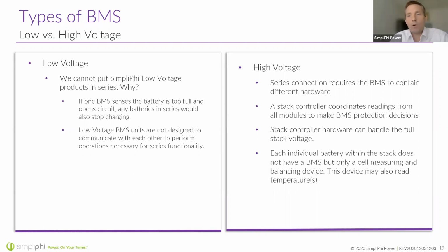High voltage units allow us to connect high voltage batteries in series, and typically the high voltage BMS is referred to as a stack controller. It coordinates the readings from all the batteries in a high voltage stack to make battery management system protection decisions. Stack controller hardware can handle very large voltages, and certainly the full stack voltage—our units go up to about 1200 volts for high voltage batteries. SimpliPhi does have a whole high voltage and large projects division. Also, each battery within the stack doesn't have its own BMS built in; the BMS is external for high voltage stacks.